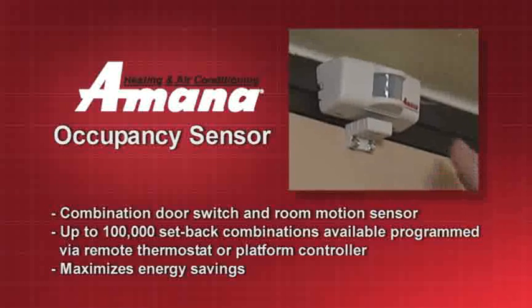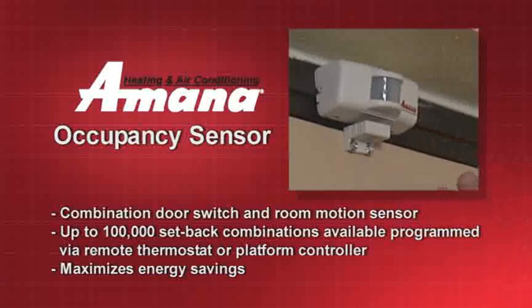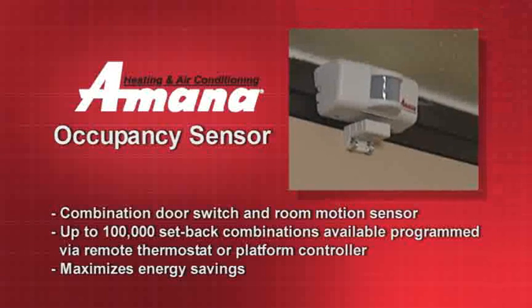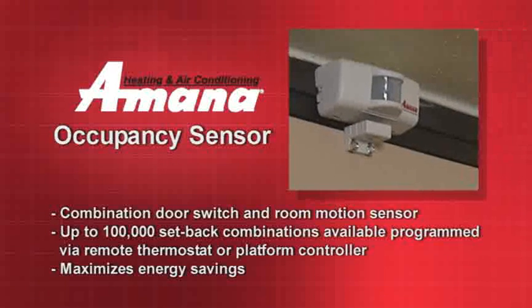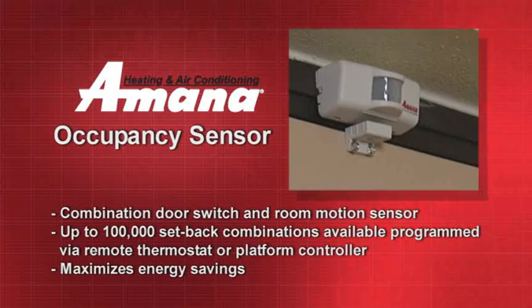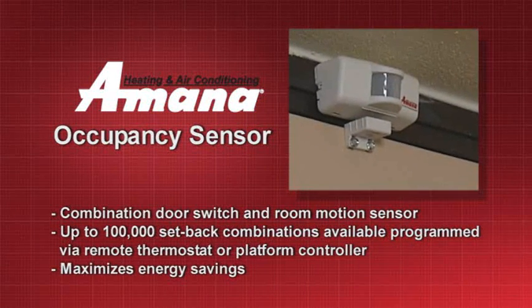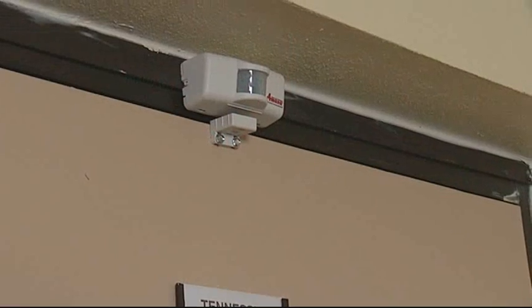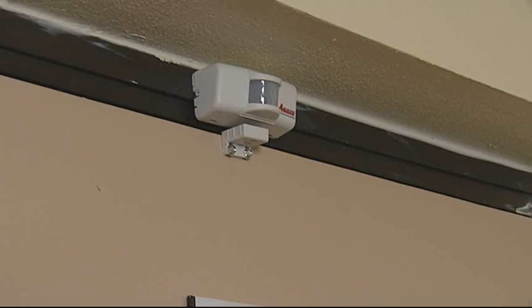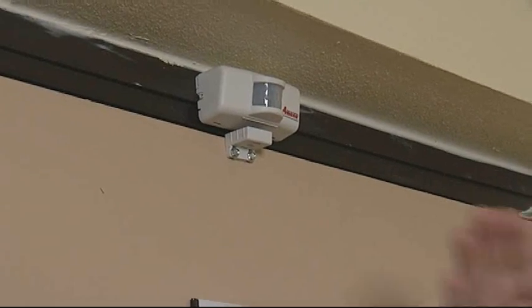And then this is a passive infrared device that's looking for motion in the room. And how it works is when we don't see motion after 5 minutes, then we're able to declare the room unoccupied and do temperature setbacks at that point. When the room is occupied, once it's declared occupied, it stays occupied until we have another door event. So that allows you to not have the room guest be uncomfortable in the room in the middle of the night.